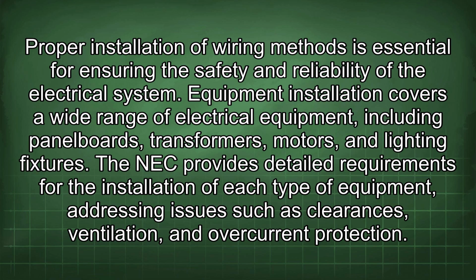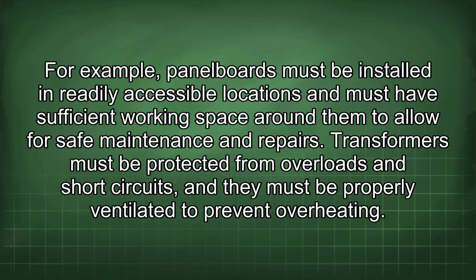Equipment installation covers a wide range of electrical equipment, including panel boards, transformers, motors, and lighting fixtures. The NEC provides detailed requirements for the installation of each type of equipment, addressing issues such as clearances, ventilation, and overcurrent protection. For example, panel boards must be installed in readily accessible locations and must have sufficient working space around them to allow for safe maintenance and repairs.